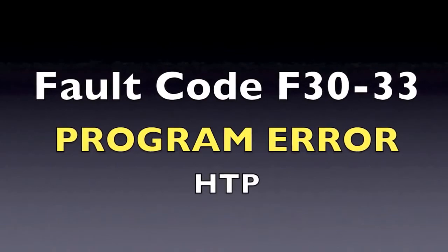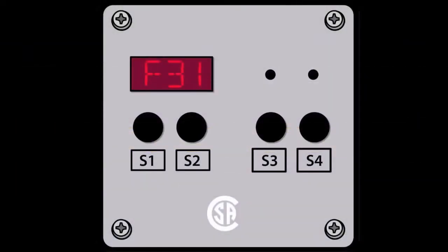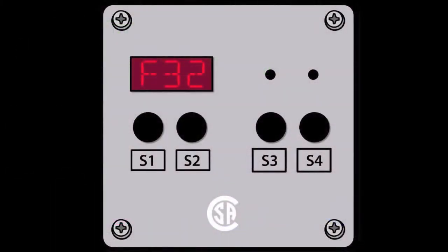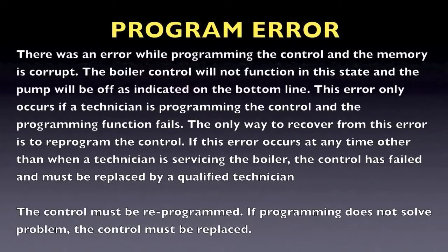If you are getting one of the following codes, an F30, F31, F32, or F33 code in the display, this indicates that there was an error while programming the controller and the memory is corrupt.